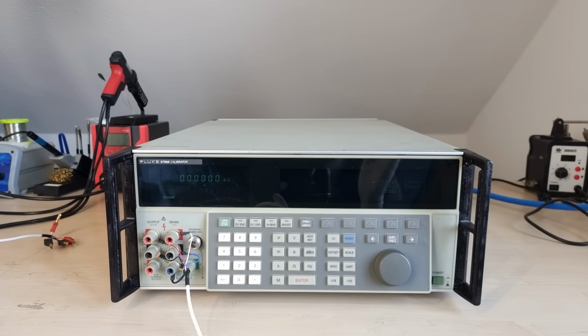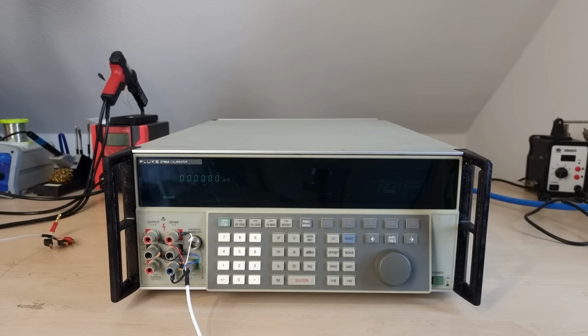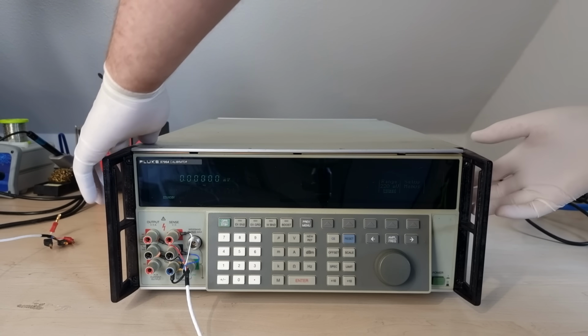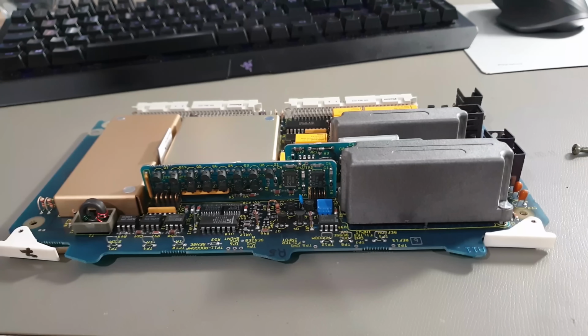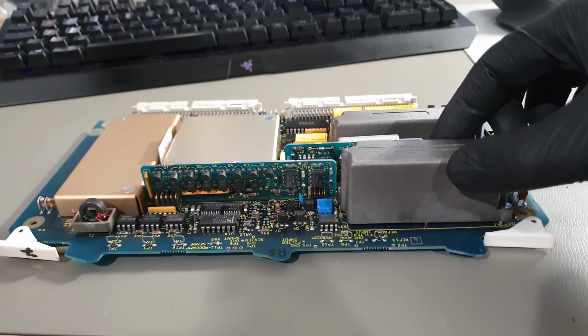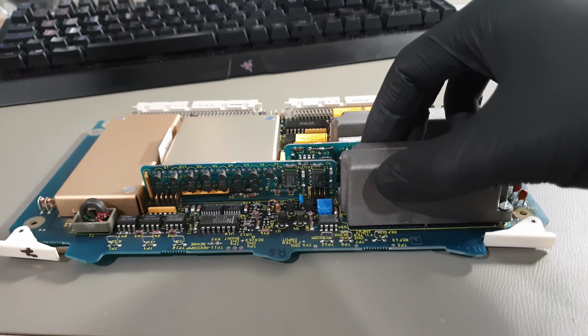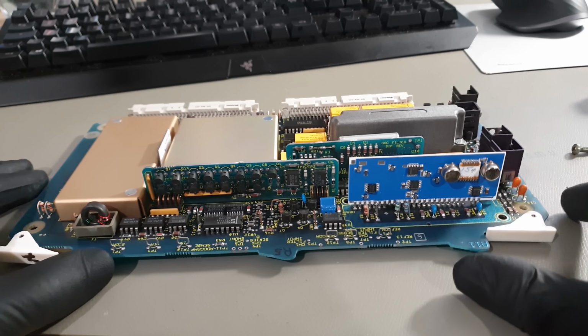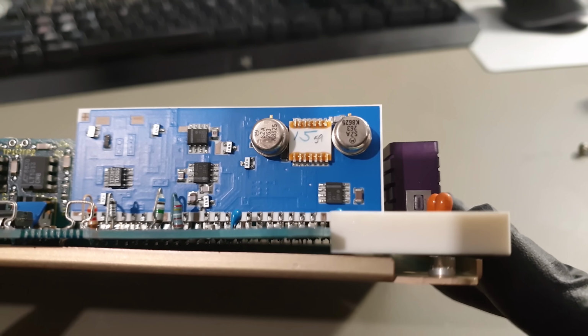Hey guys, last year we were able to give this magnificent Fluke multifunction calibrator a well-deserved in-depth refurbishing. Now there is nothing preventing it from doing its job and spreading that sweet accuracy for another 30 years. Except maybe that there is no more accuracy left to spread. You see, even just opening the enclosure once and looking at the internals lets some of those volatile ppm escape. And the open heart surgery that we performed was much more impactful than that. So now the calibrator itself needs calibration and adjustment.